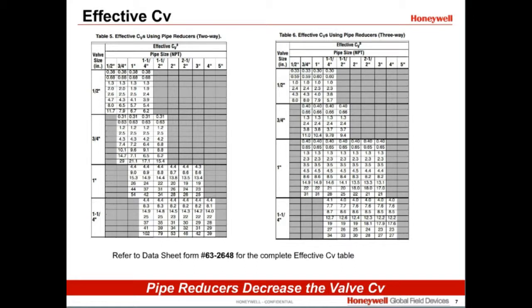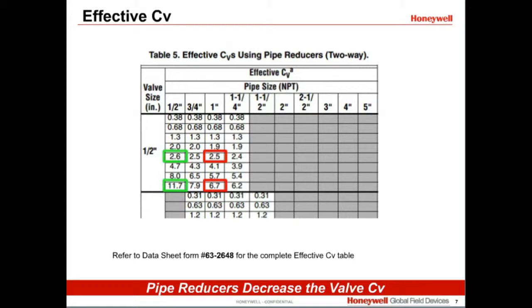If you look at a particular valve size, you'll notice that as the CV increases, the impact on the CV reduction becomes more significant. For example, a half-inch size valve used in a 1-inch pipe system will result in a 2.5 effective CV instead of a nominal 2.6 CV. In a similar system, an 11.7 CV valve will yield only an effective CV of 6.7.